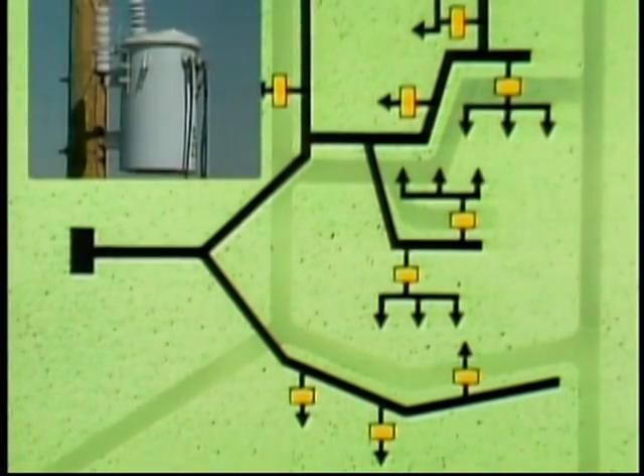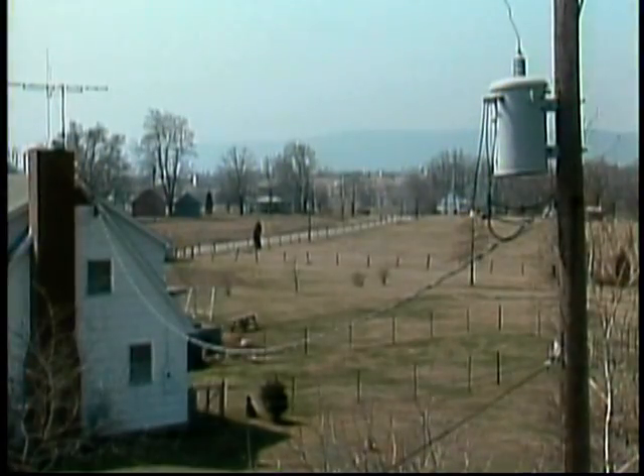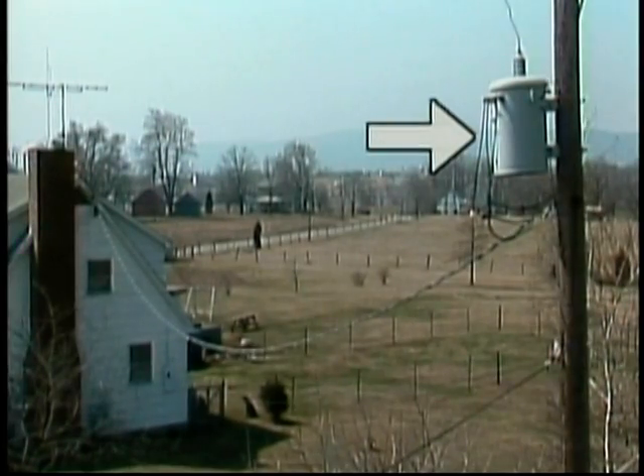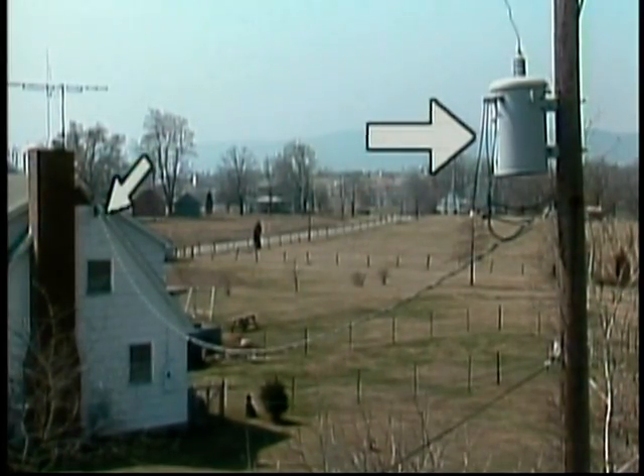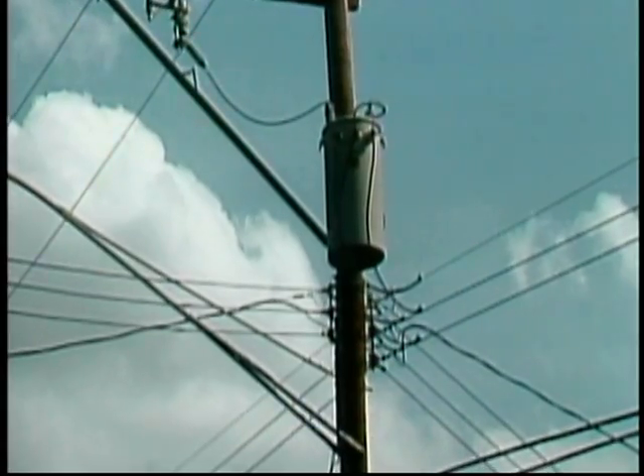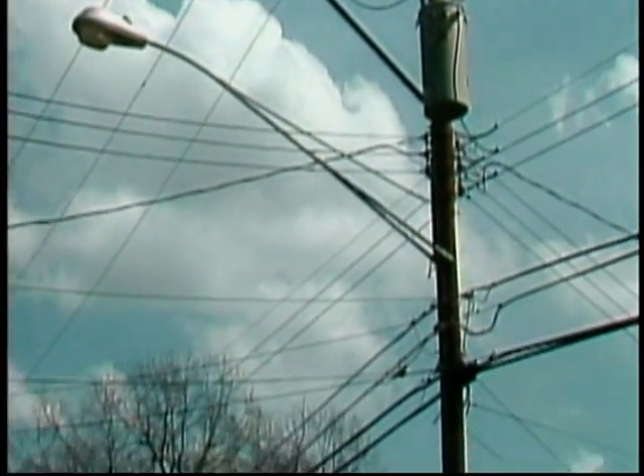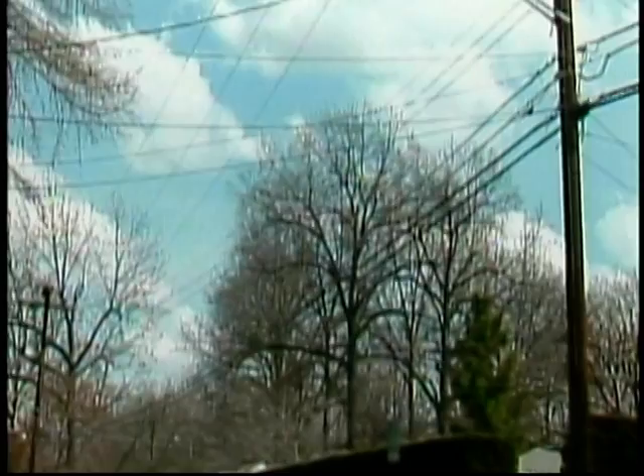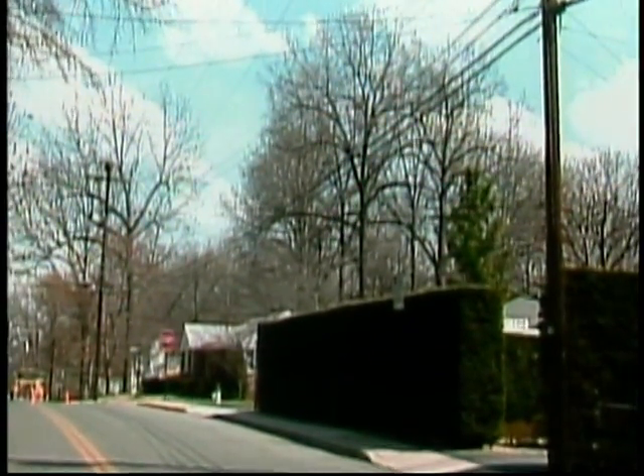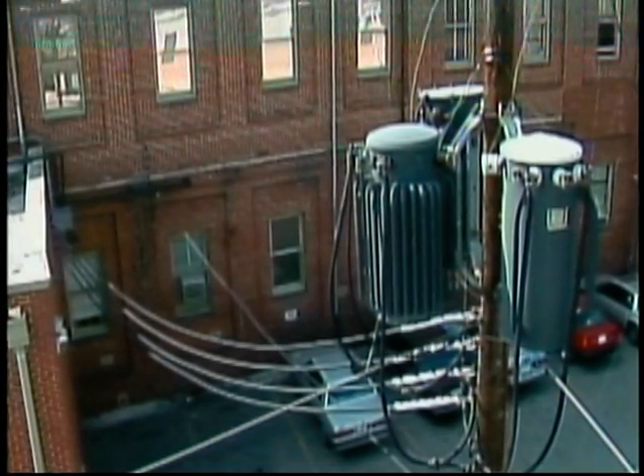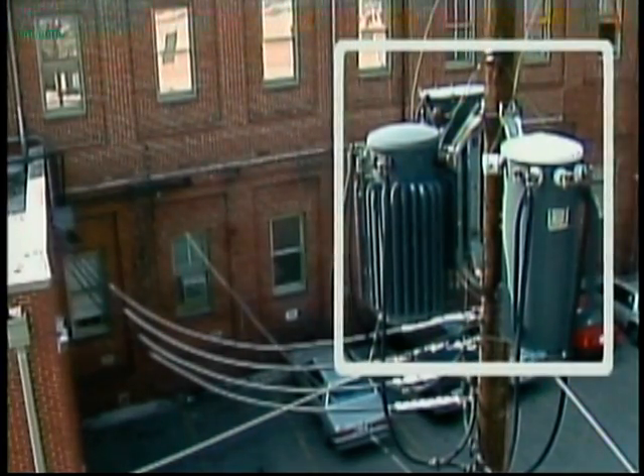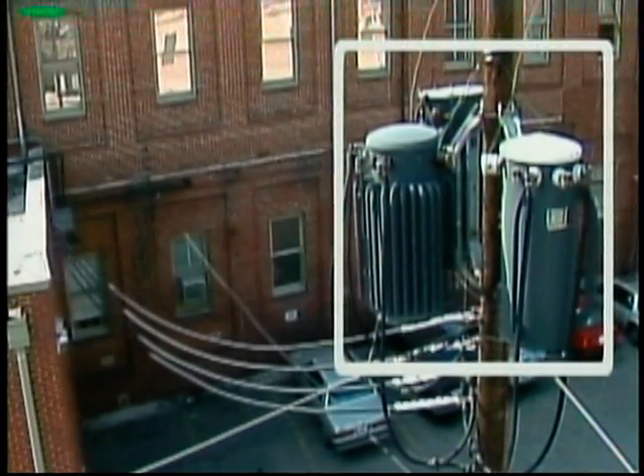Overhead distribution transformers may be found anywhere on a distribution primary, wherever voltage needs to be stepped down to usable voltage for a customer. In rural areas where individual customers are far apart, a single transformer may supply power through a service drop to only one customer. In more populated areas, transformers may supply many customers through a secondary main with multiple service drops. Some customers require three-phase power. In this case, transformers may be banked together to provide three-phase power.